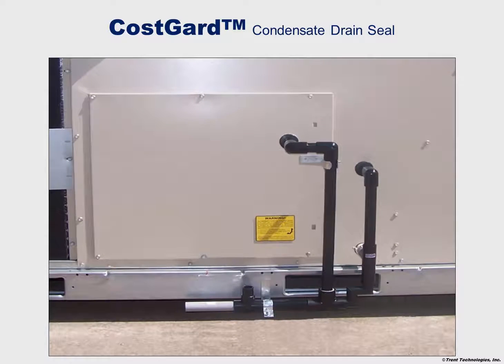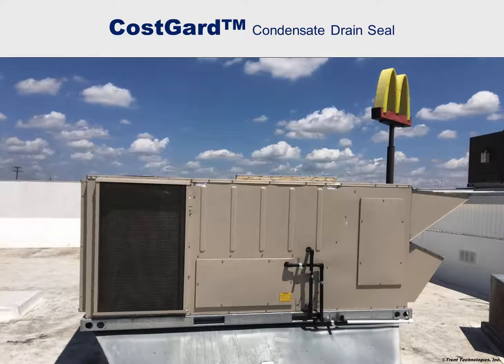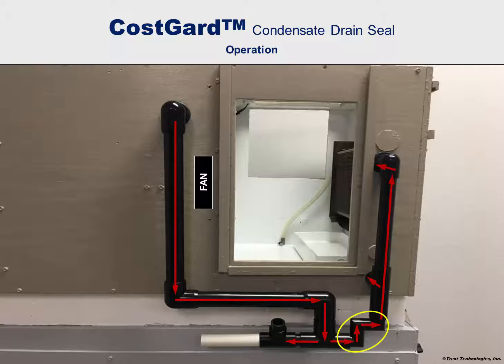This seal protects the building owner or user against undue cost in terms of maintenance effort, property damage, early equipment replacement, and health care. For this reason, the word CostGard is used to identify this seal. The CostGard Condensate Drain Seal, installed on this simulated air handler, helps explain how the device functions. A small quantity of air is taken from the positive pressure side of the fan. A portion of this air is discharged through the condensate drain pipe to ensure that outside air and pollutants are not drawn into the system. The remainder of the air is directed through the mitered elbows into the air conditioning unit. The air pressure loss in these elbows ensures that the air velocity entering the condensate drain pan is too low to cause condensate blowing. At the same time, its air seal allows condensate to flow freely from the drain pan.